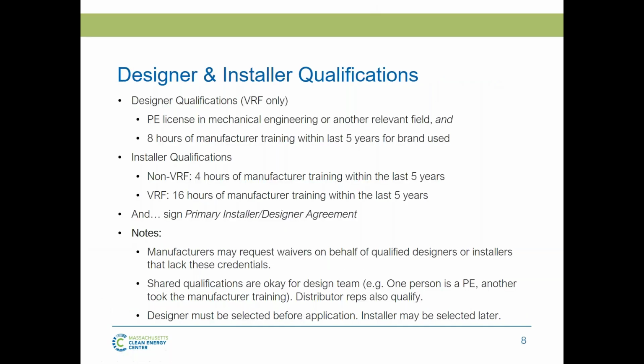So, getting into the details of qualifications. First of all, for system designers and installers. For designers, this is only a role for VRF systems. For Minisplits, we don't have a designer role. Often it's the contractor doing a design for a design-build project, let's say. But for VRF, we want to make sure that the designer has a PE license, usually in mechanical engineering, and 8 hours of manufacturer training within the past 5 years, for the manufacturer brand that's being installed.